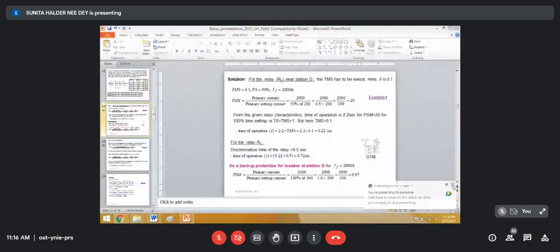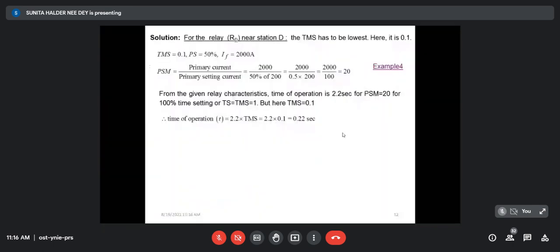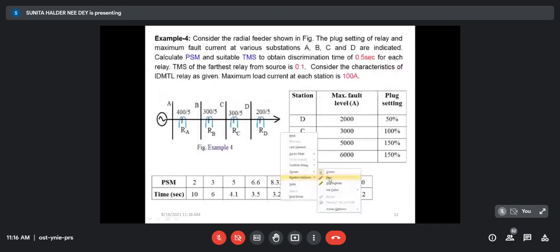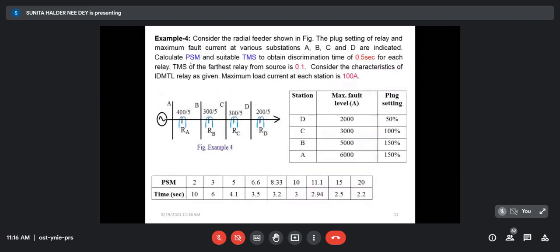So we have set the relay at station D with PSM of 20 and TMS of 0.1, giving an operating time of 0.22 second. We have to calculate PSM for RD — already done — and PSM and TMS for RA, RB, and RC. We have configured RD as the primary relay.